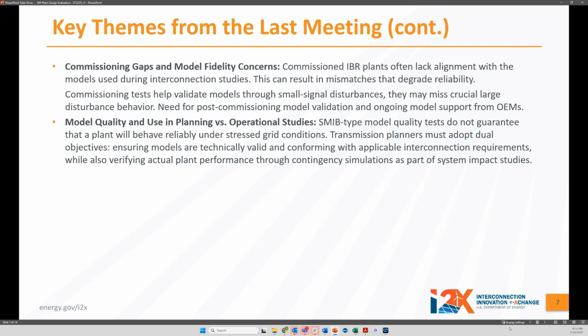The last highlight from the discussion section of the last meeting was being clear about the difference between modeling requirements, model quality tests, and studies. We often have a single machine infinite bus type model quality test - these not only check the quality of the models, but can also make sure the plant, as modeled, meets a set of interconnection or performance requirements. So you can think of it as performance conformity testing of the plant, making sure it's meeting a certain response time, ride-through performance, etc.